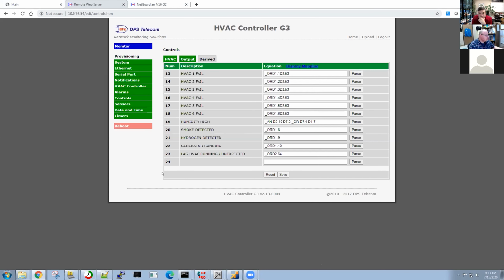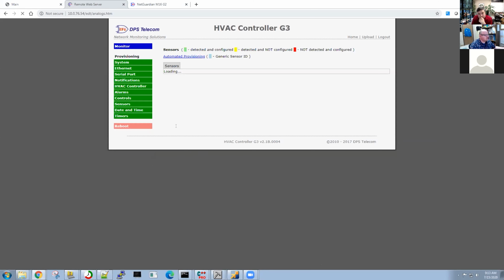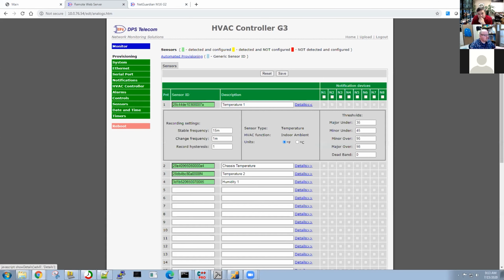That's what that's about. Beyond that, we've got some other things we could hit. There's the sensors here as well. Each of these sensors has thresholds for generating its own alarm data. You can set up notification on a sensor basis too. So as you said, it gets cool on one side of the building, hot on the other. If we ever ended up with it getting particularly hot around one sensor, that sensor itself can generate notifications: hey, it's hot here, you might want to check if the system is running as expected, or if something else is going on.